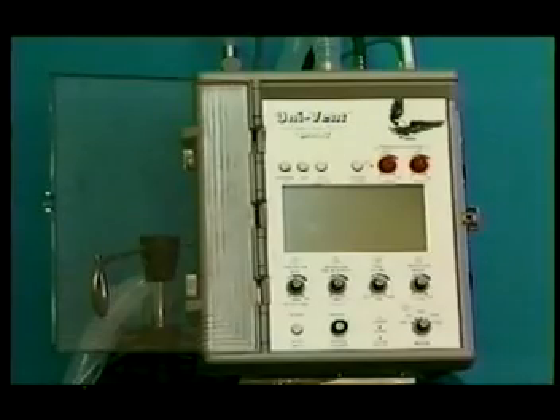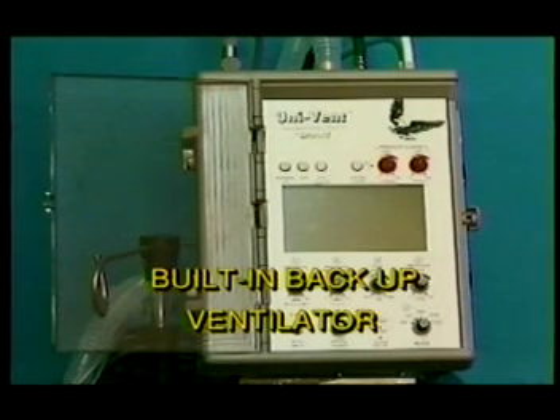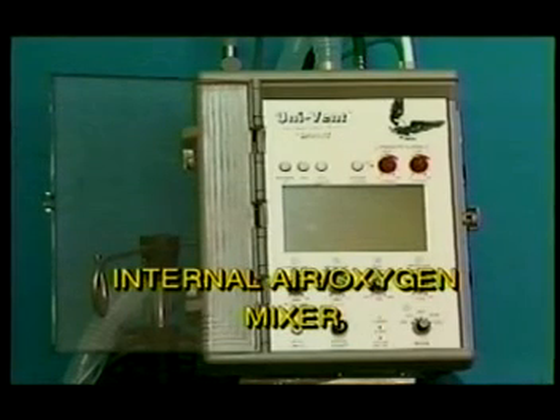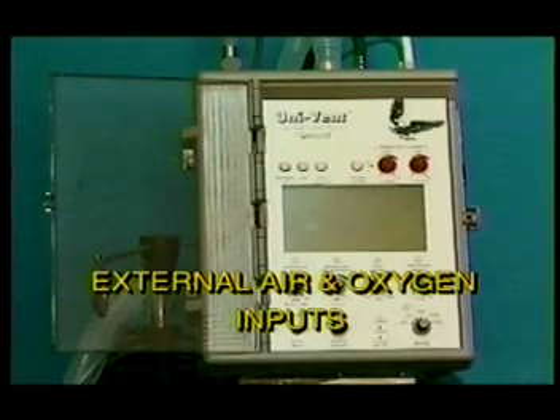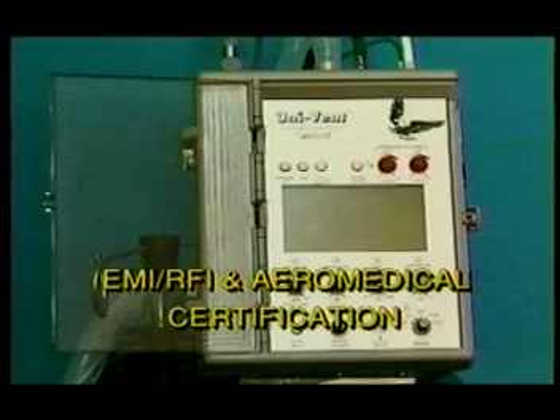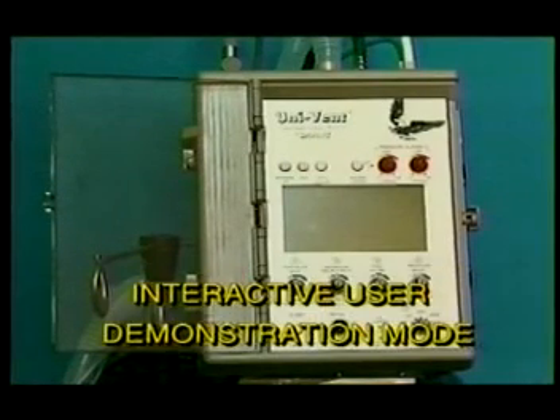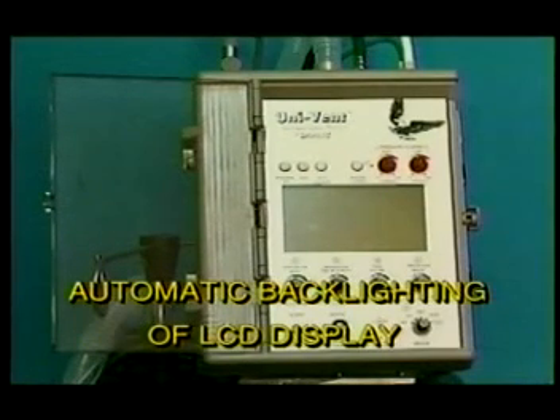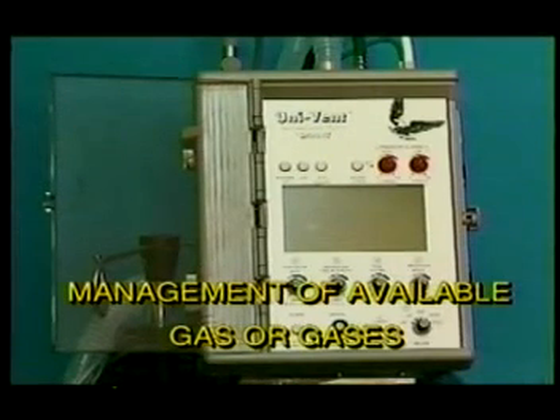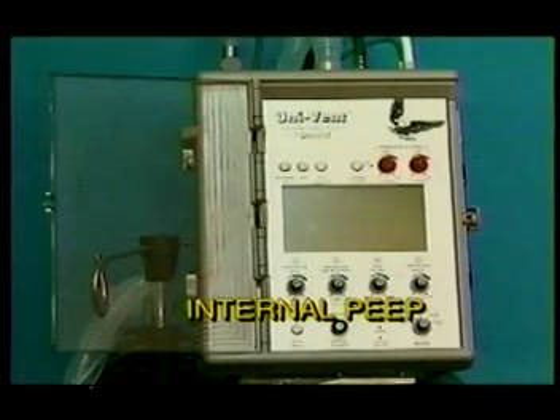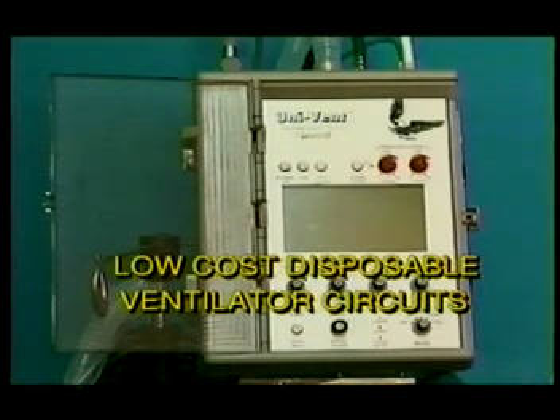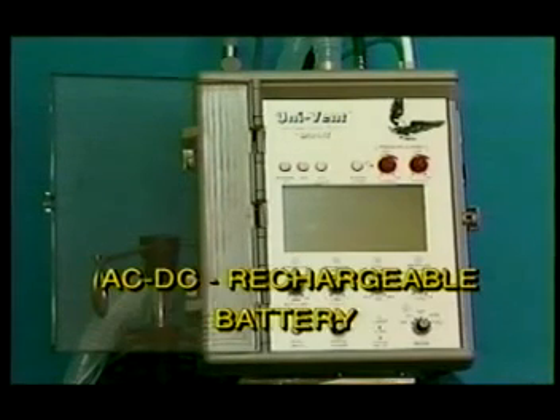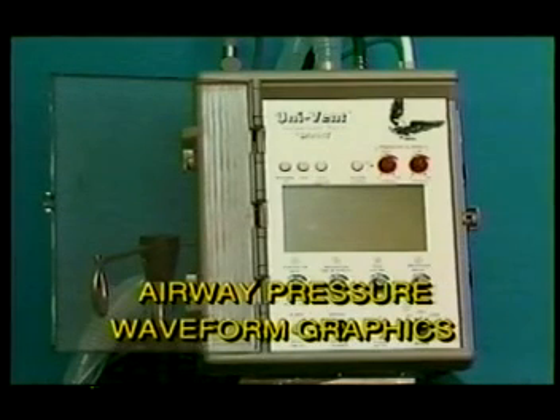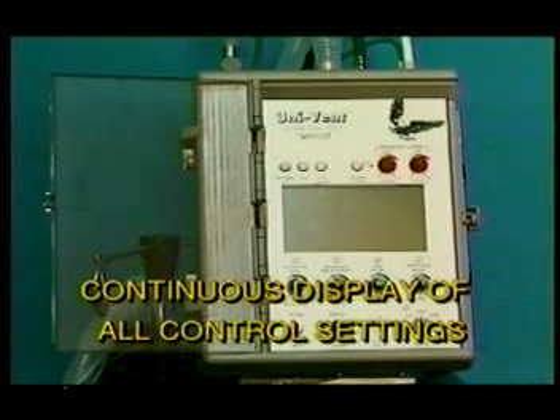The Eagle has many features that maximize patient safety and ease of operation. These features include operation from internal compressor, built-in backup ventilator, internal air oxygen mixer, external air and oxygen inputs, automatic altitude compensation, EMI, RFI, and aeromedical certification, interactive user demonstration mode, automatic backlighting of LCD display for viewing under any condition, management of available gas or gases to assure that the set tidal volume is always delivered, internal PEEP, which eliminates the need for external PEEP valves, low-cost disposable ventilator circuits, apnea backup mode, AC-DC rechargeable battery, airway pressure waveform graphics, and continuous display of all control settings.